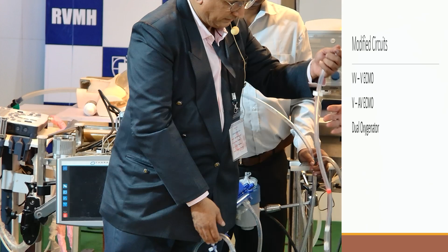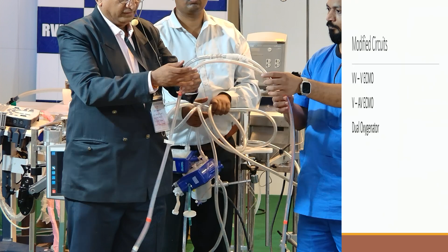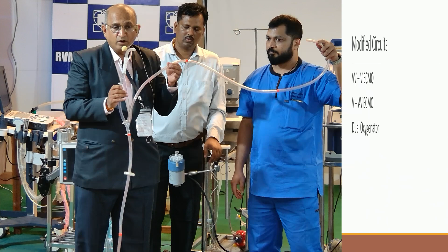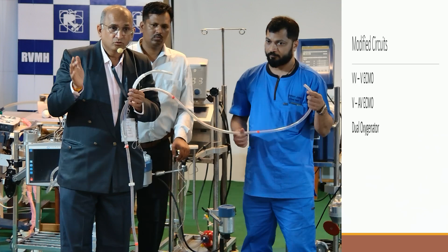Then from here it goes to the oxygenator. From the oxygenator it comes out, and it goes to the patient. This is the one where you measure P2, pre-oxygenator. This is the one where you measure P3, post-oxygenator pressures. Okay, and then it goes to the patient. Okay, you can place a flow sensor.